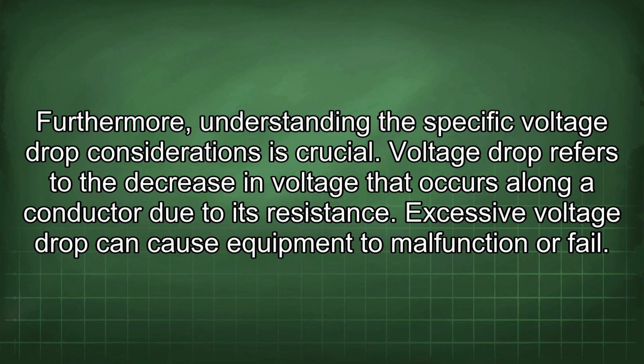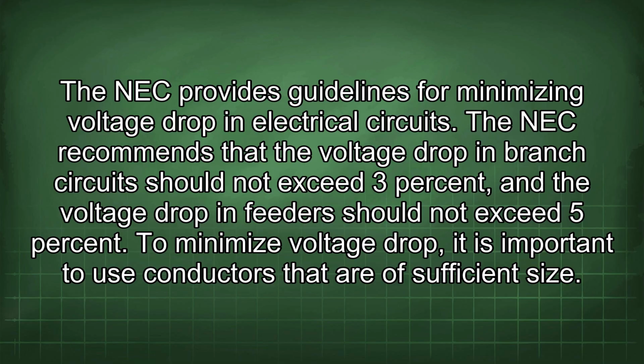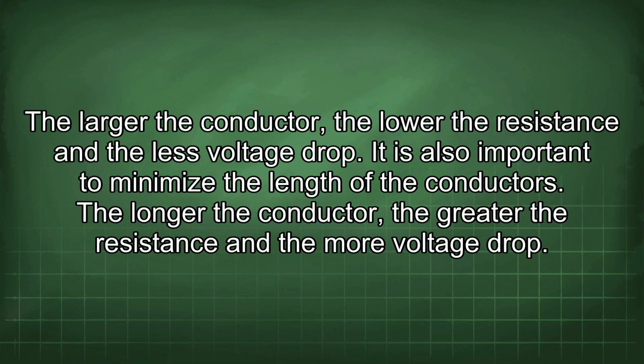Furthermore, understanding the specific voltage drop considerations is crucial. Voltage drop refers to the decrease in voltage that occurs along a conductor due to its resistance. Excessive voltage drop can cause equipment to malfunction or fail. The NEC provides guidelines for minimizing voltage drop in electrical circuits. The NEC recommends that the voltage drop in branch circuits should not exceed 3% and the voltage drop in feeders should not exceed 5%. To minimize voltage drop, it is important to use conductors that are of sufficient size. The larger the conductor, the lower the resistance and the less voltage drop.